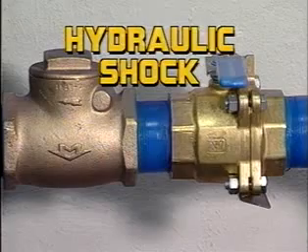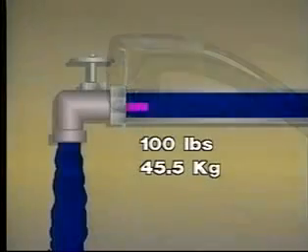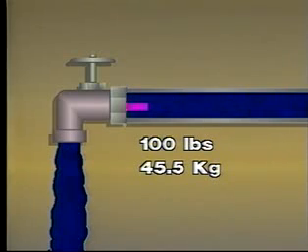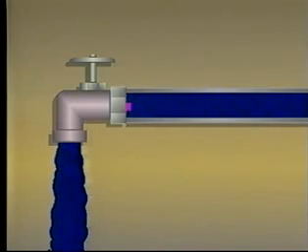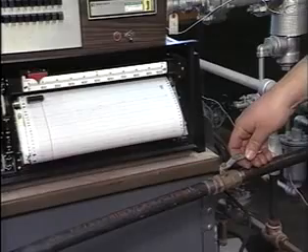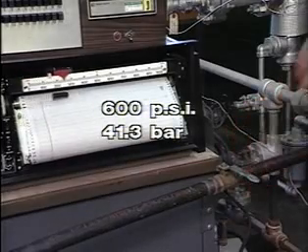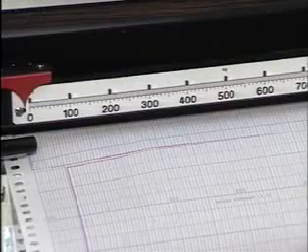Hydraulic shock occurs when a valve is closed too abruptly. When a water valve is open, a solid column of water moves from its source at the main to the valve outlet. This could be 100 pounds of water flowing at 10 feet per second or about 7 miles per hour. Closing the valve suddenly is like trying to instantly stop a 100 pound hammer. A shock wave of about 600 psi slams into the valve and rebounds in all directions, expanding the piping and reflecting back and forth along the length of the system until its momentum is dissipated.